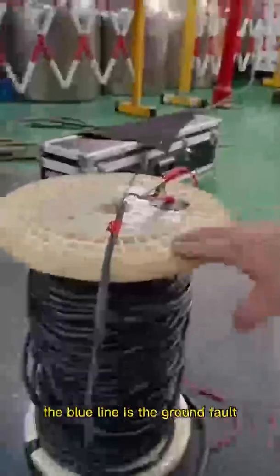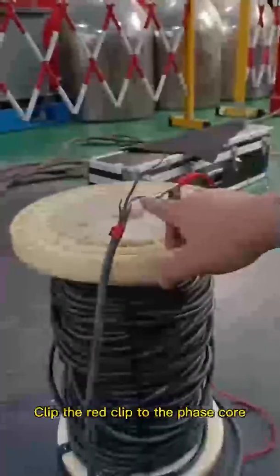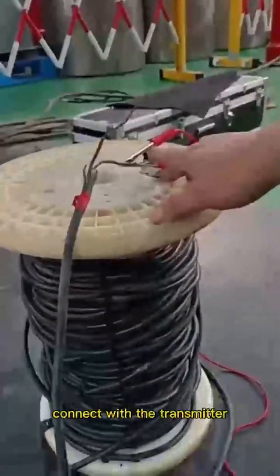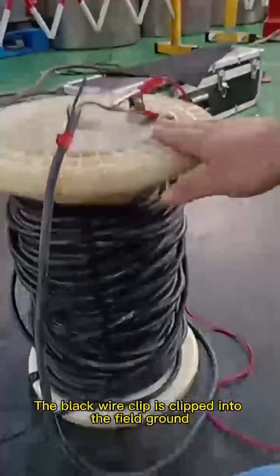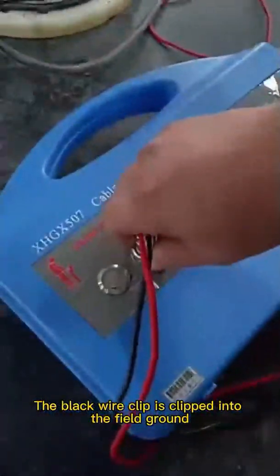Now we simulate finding ground faults with the A-frame. Simulate the site. The blue line is the ground fault. Clip the red clip to the phase core and connect with the transmitter. The black wire clip is clipped into the field ground.